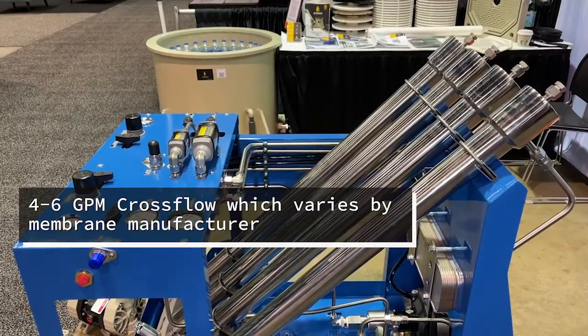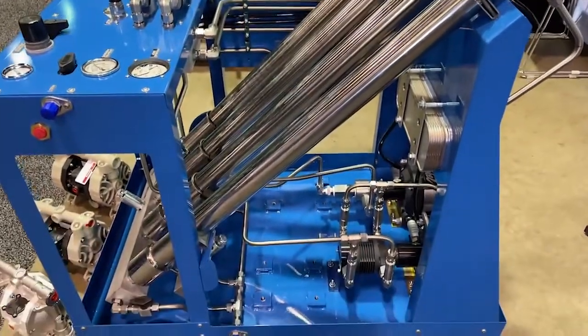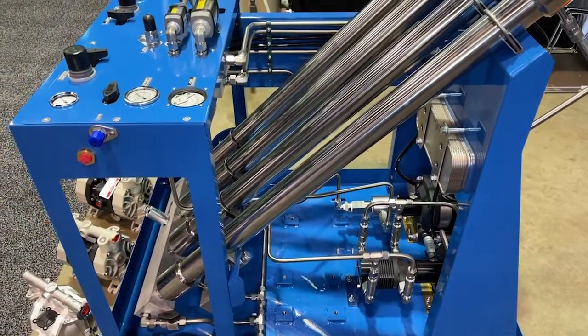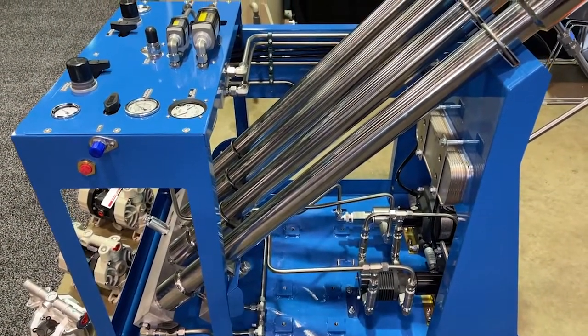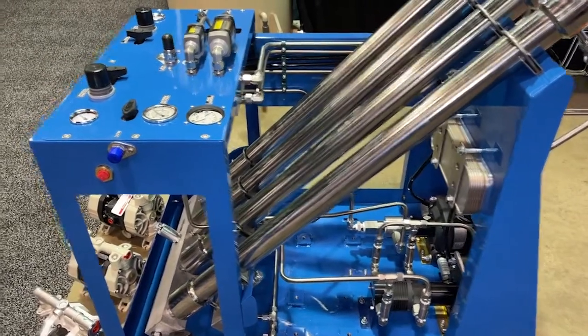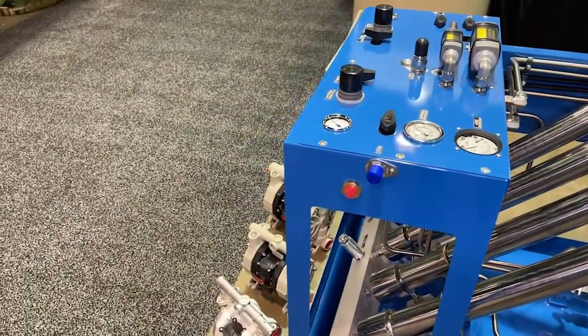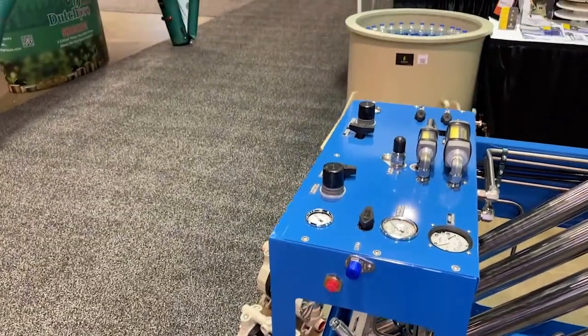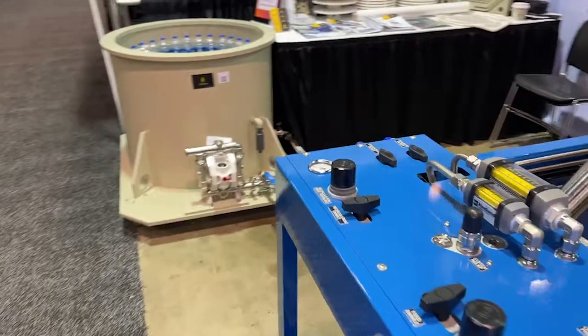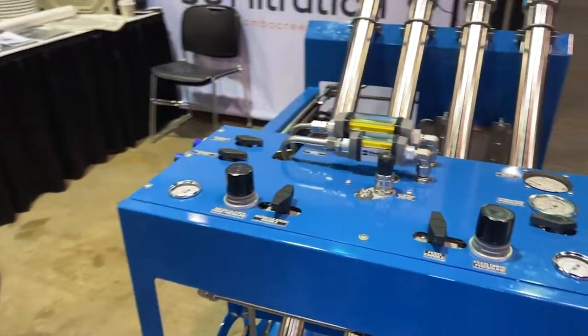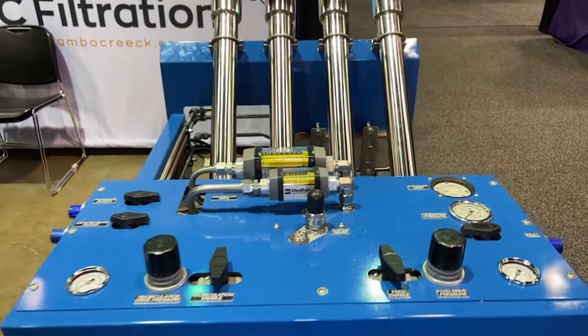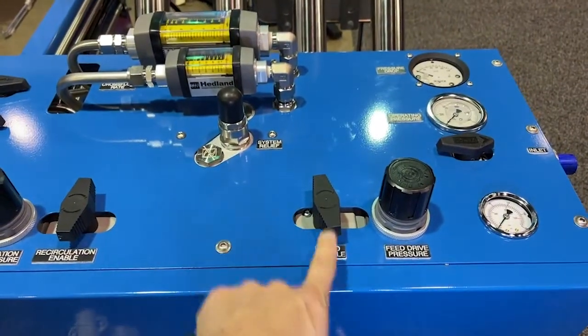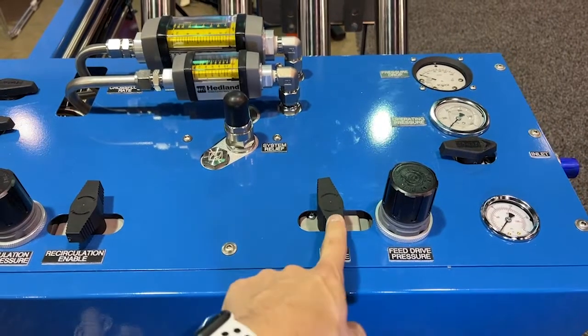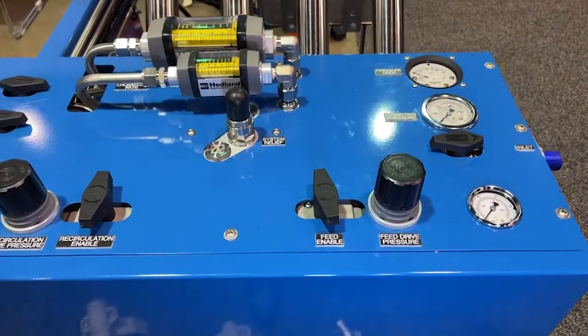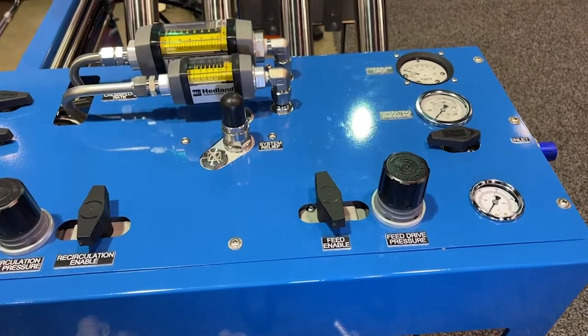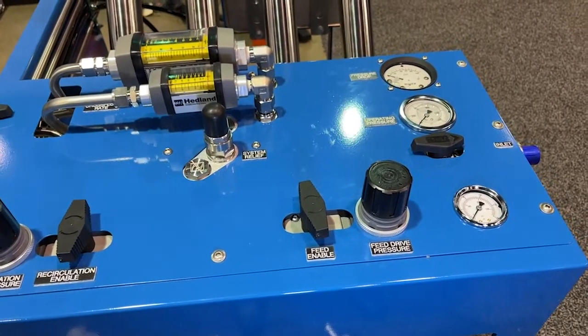But then the system as a whole with the other pump, one's called a loop pump, a recirculating pump, and that's creating your cross flow. And then the other pump is your feed pump, which does the function of suctioning the fluid into your system, and it goes out the other end. And so the operation of it, once you know how the feed and the loop pump work: since this is a pneumatically driven pump, with these valves and with air, you control the feed. And so that's going to determine how much your final concentration is going to be.